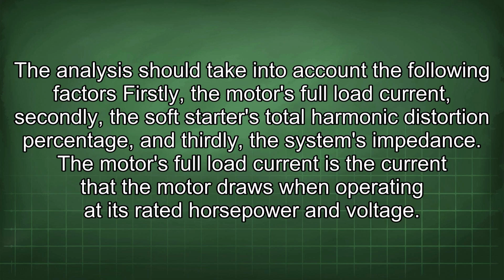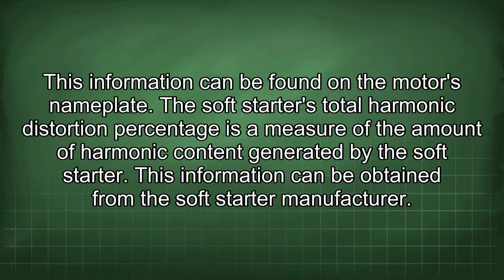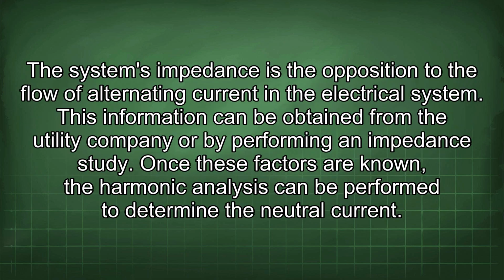The motor's full load current is the current that the motor draws when operating at its rated horsepower and voltage. This information can be found on the motor's nameplate. The soft starter's total harmonic distortion percentage is a measure of the amount of harmonic content generated by the soft starter. This information can be obtained from the soft starter manufacturer. The system's impedance is the opposition to the flow of alternating current in the electrical system. This information can be obtained from the utility company or by performing an impedance study.